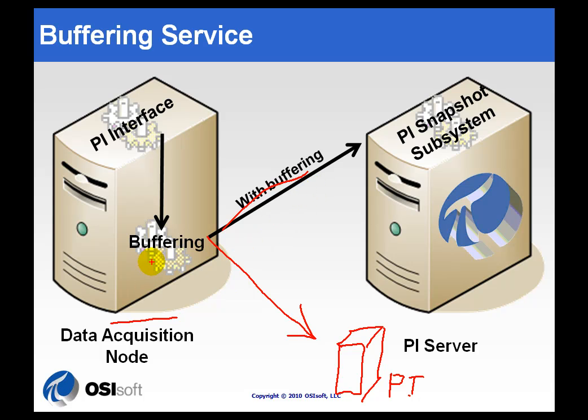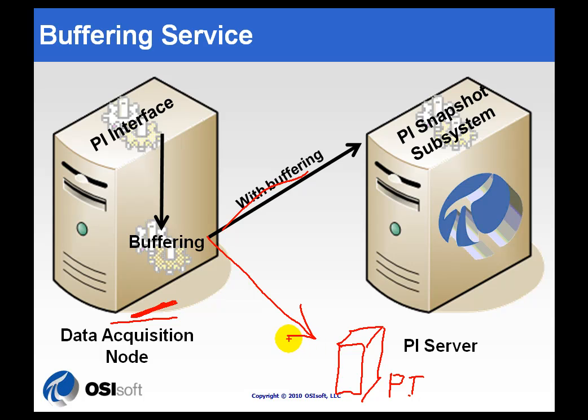If instead of the PI Buffer Subsystem you use the API Buffer Server, that does not do data compression on the Interface Node. It sends raw, uncompressed data to both servers. Since data compression depends on the order in which you get certain data, the same raw data sent to two different PI Servers with slightly different current values or most recent archive values could actually end up with slightly different stored data.